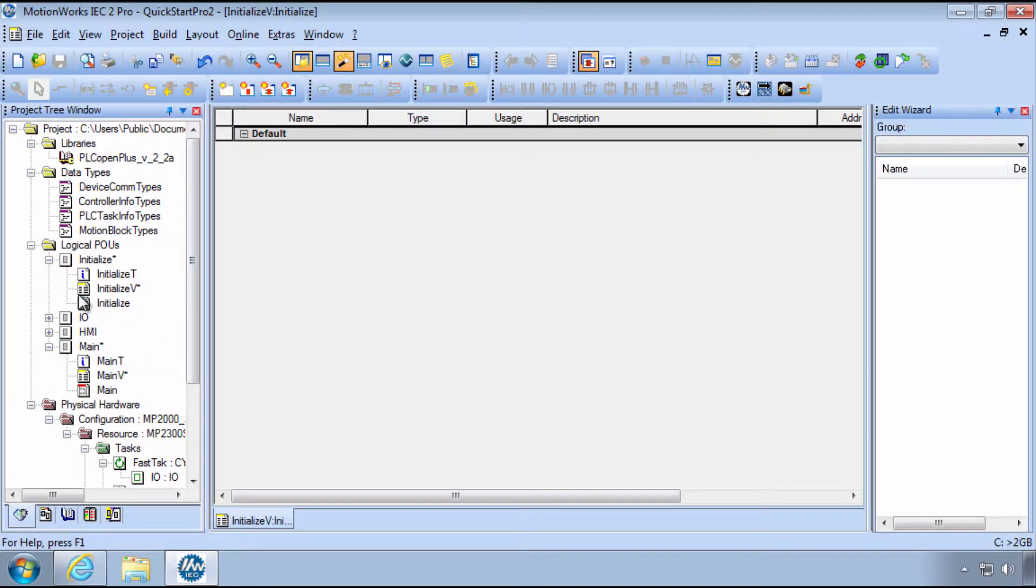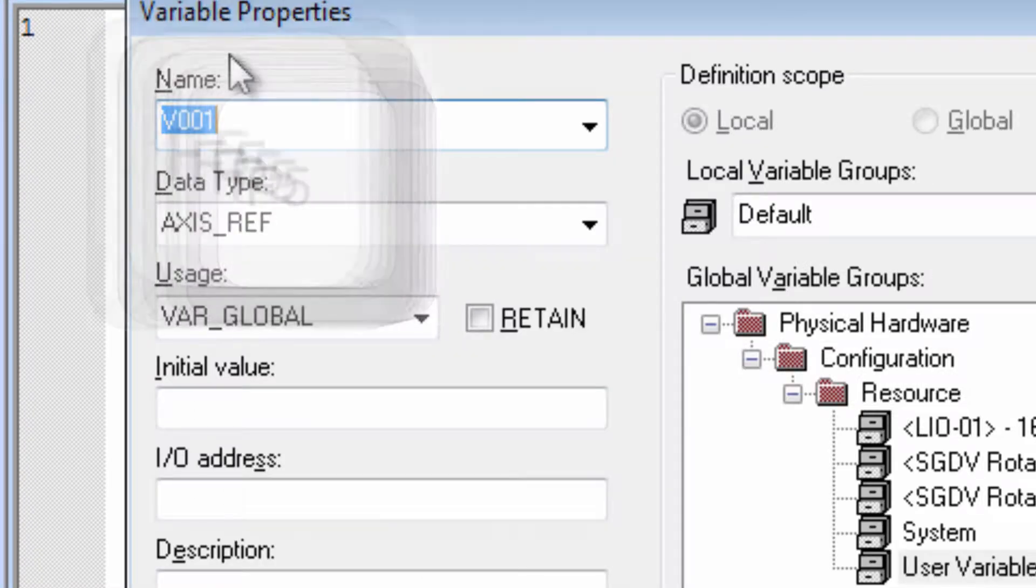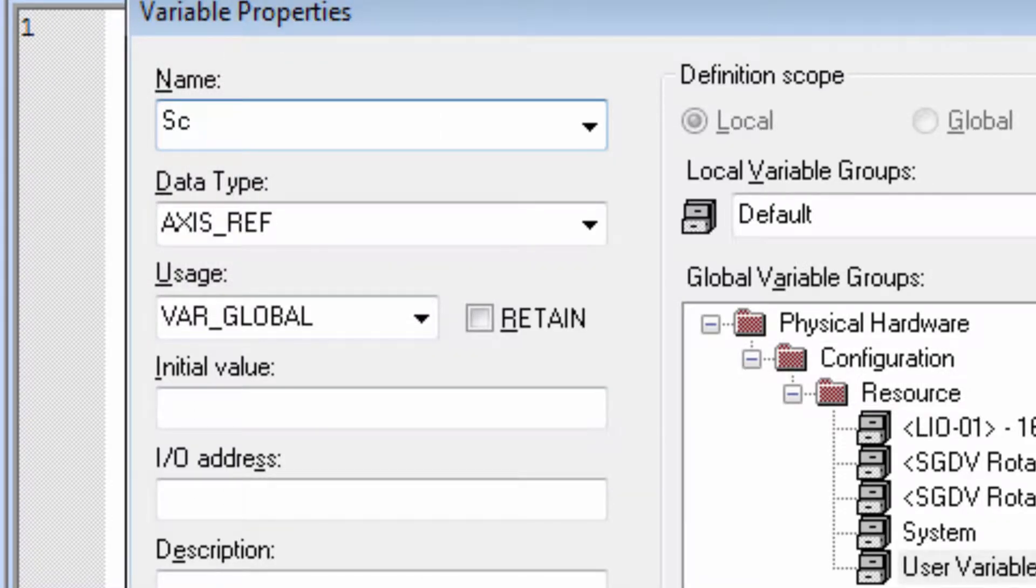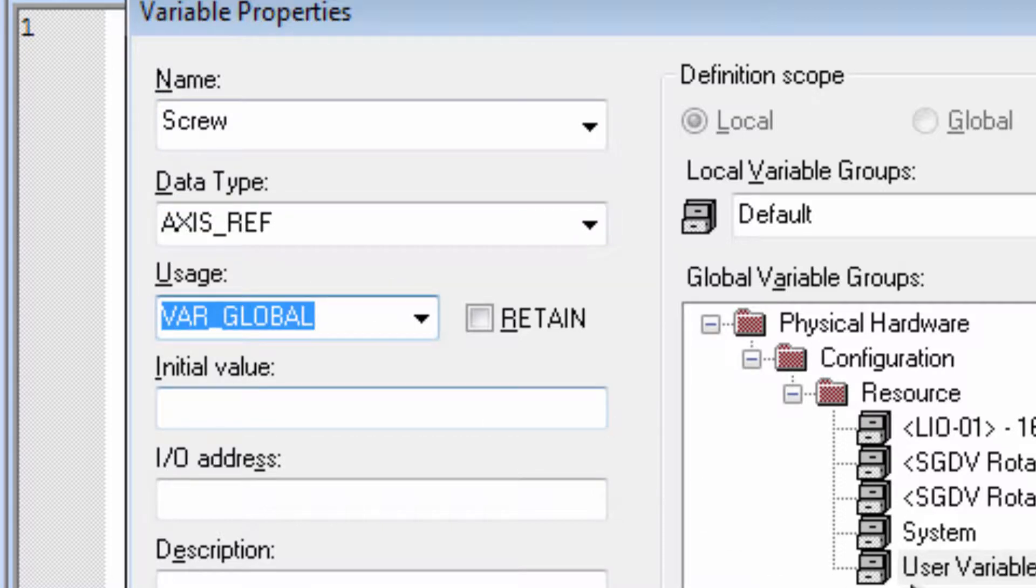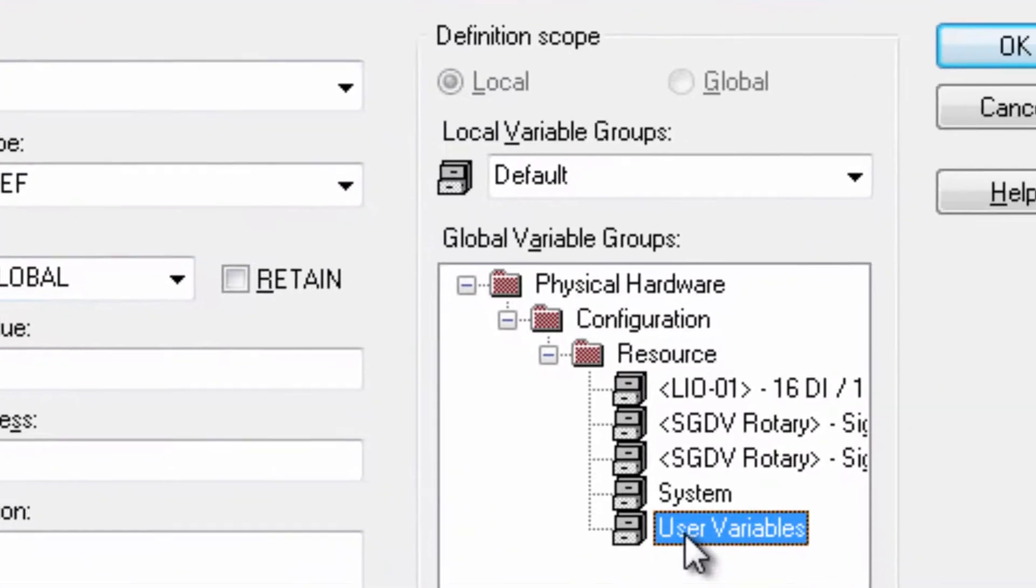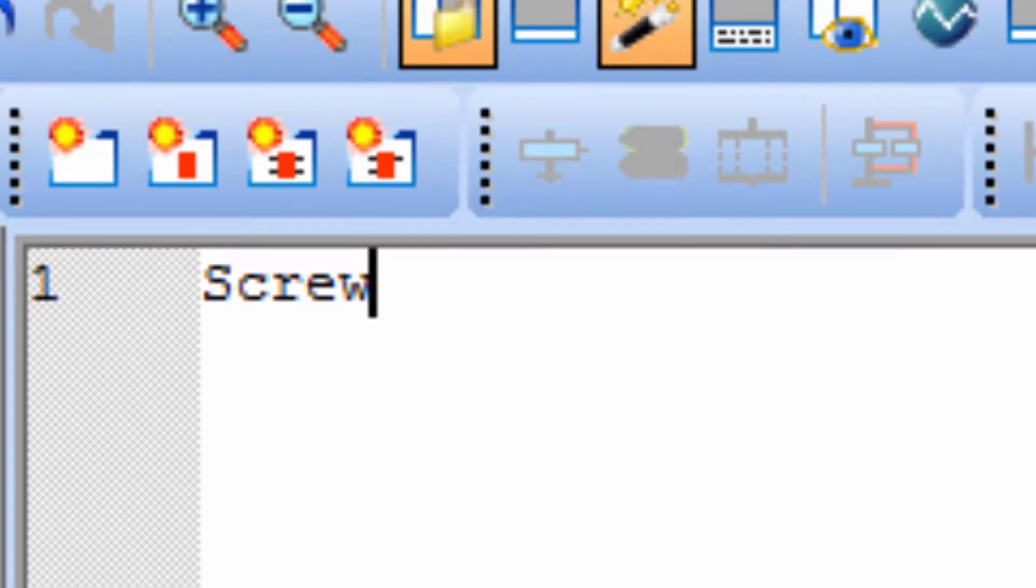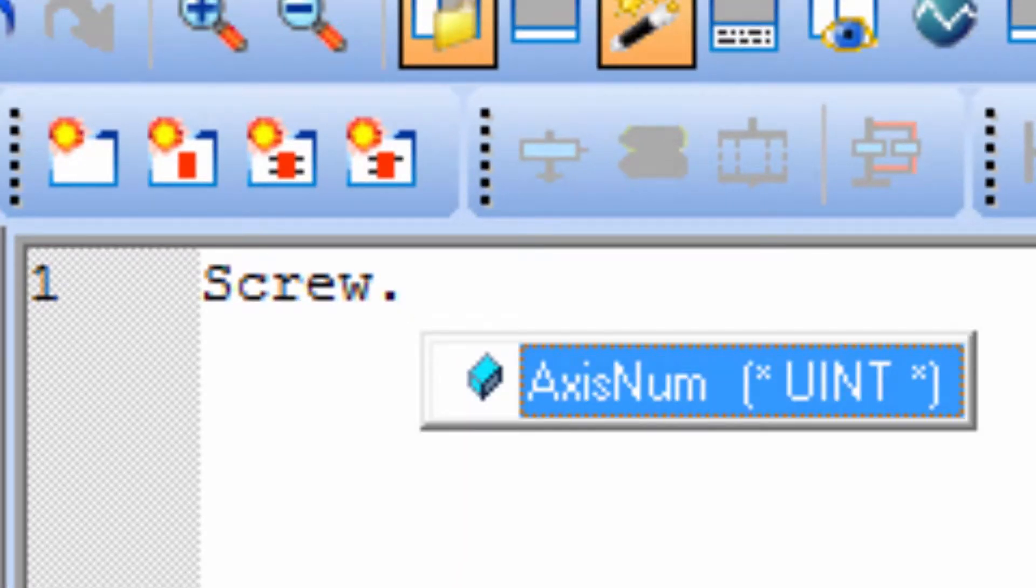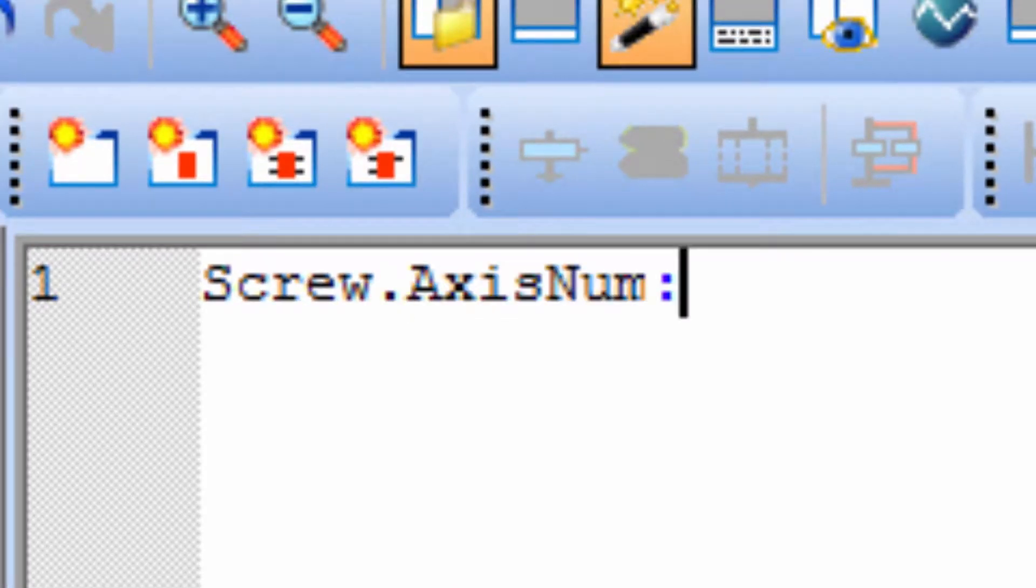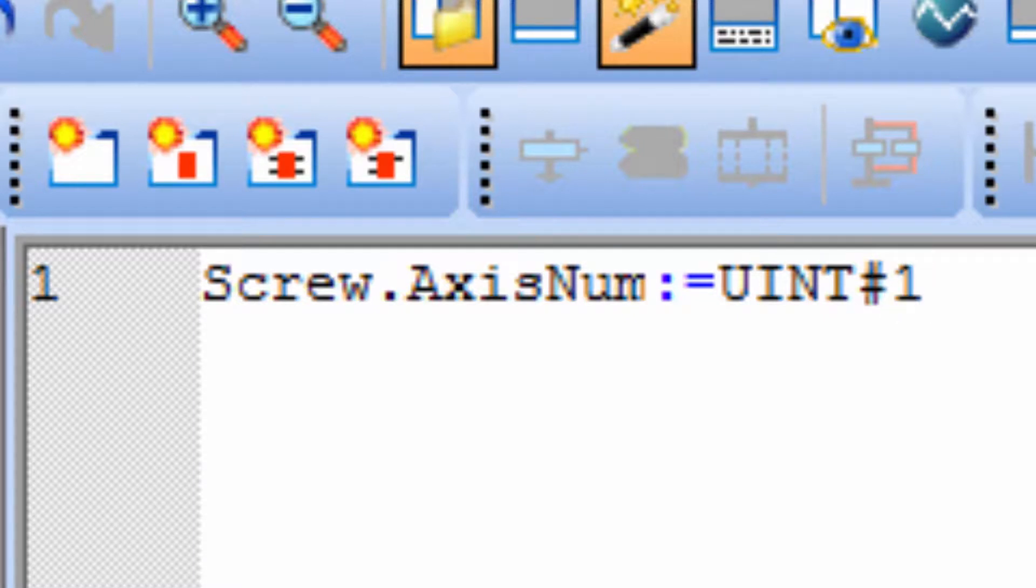In the Initialize POU, hit the F5 key to name the variable with AxisRef data type and usage var global in the user variable group. Type dot and choose the AxisNum structure element, finishing the command with colon equals uint pound and the logical axis number, ending the line with semicolon. The variable can now be used anywhere an axis is required.